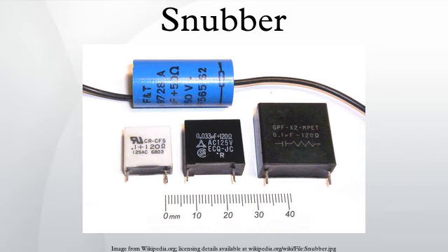A snubber is a device used to suppress some phenomenon, such as voltage transients in electrical systems, pressure transients in fluid systems, or excess force or rapid movement in mechanical systems. Snubbers are frequently used in electrical systems with an inductive load where the sudden interruption of current flow leads to a sharp rise in voltage across the current switching device, in accordance with Faraday's law.